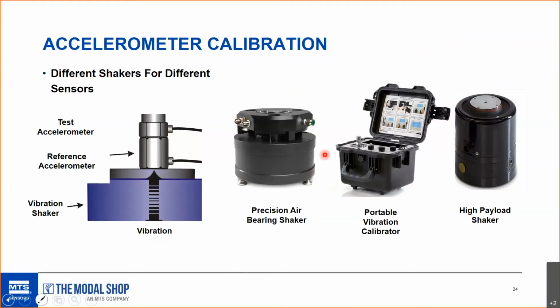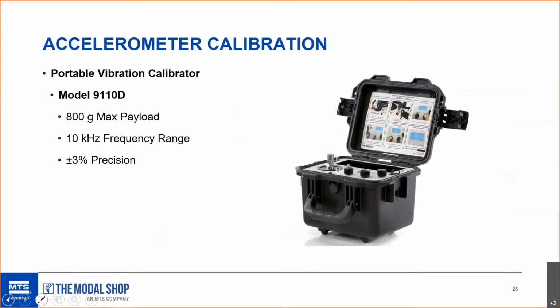A precision air bearing shaker, which is used in our 9155 laboratory grade systems, and we'll talk about its specs later. And then the portable vibration calibrator, which Mike is the champion of and the expert on in industrial calibration. And we also have a high payload shaker for those accelerometers that cannot be calibrated by the other two. So we'll do a rundown now of the specs, a little bit of what they look like. You want to take a run at the PVC, Mike?